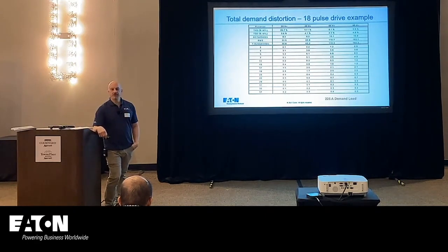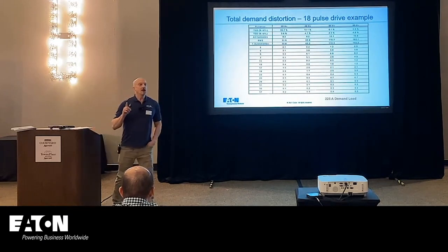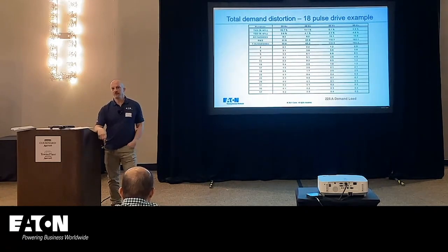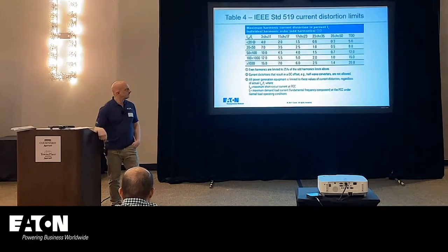The other thing about this is, you might say, well, I want my drive to have less than 5 or 6% distortion. You go, well, okay, it is at 60 hertz, but why do you buy a drive? Do you buy a drive to run it at 60 hertz? No. If you do, I'll sell you a whole bunch of other stuff, because that's a really bad waste of money. You run a drive at less than 60 hertz to save energy, or you change frequency to control the speed, right?